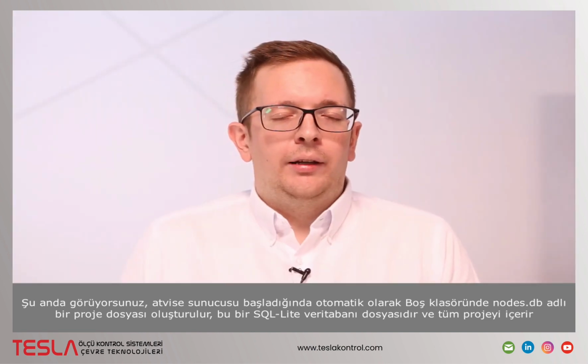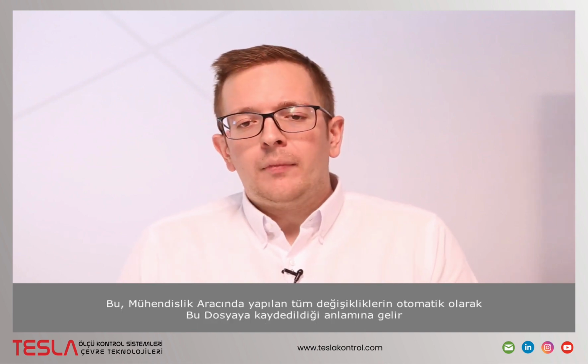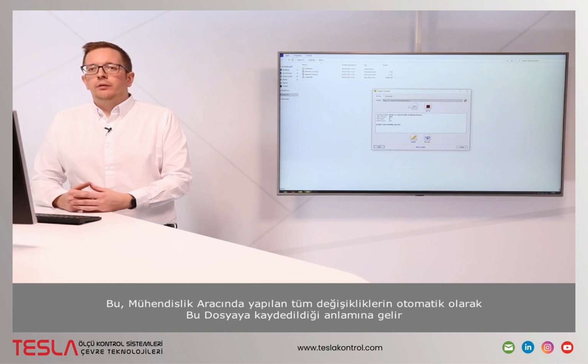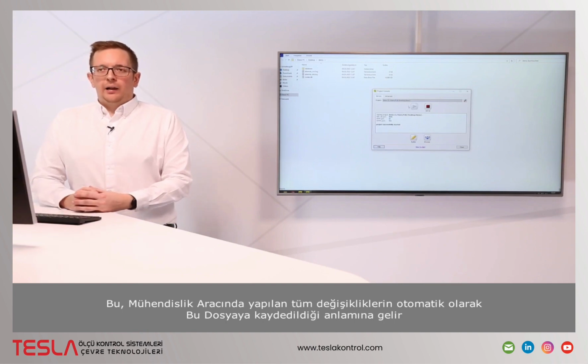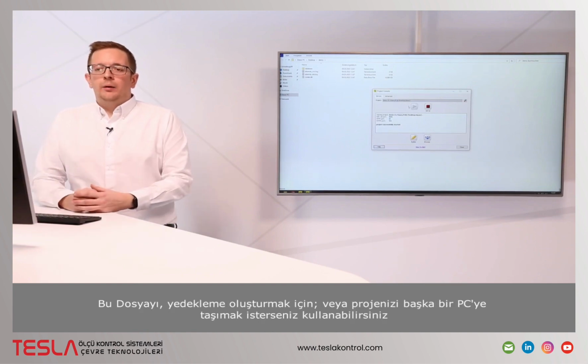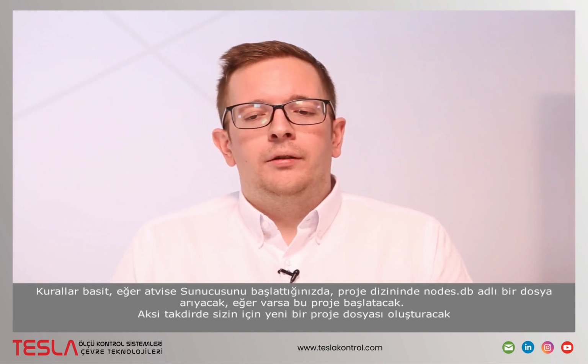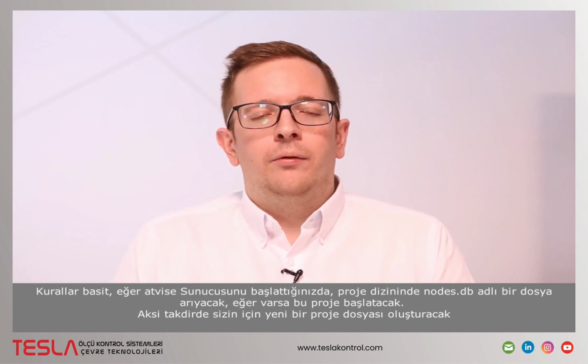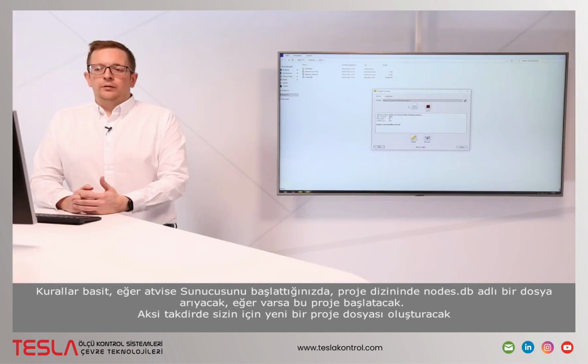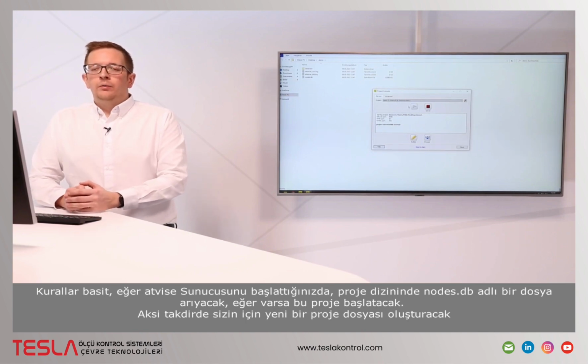It is a SQLite database file and it contains the whole project. This means all changes done in the engineering tool are automatically saved in this file. You can use this file for creating backups or if you would like to move your project to any other PC. The rules are simple. If you start the Atvise server, it is looking for a file called nodes.db in the project directory. If it's available, this project will be started. Otherwise, a new project file will be created for you.